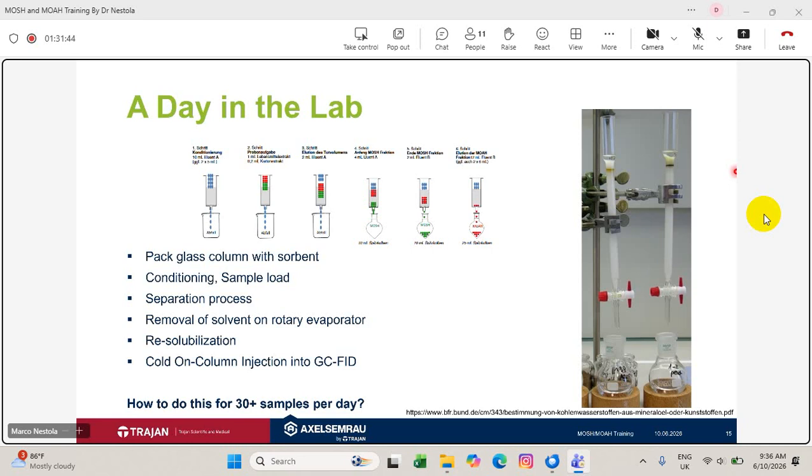You are getting nice alkanes in the beginning, and then they are getting smaller and smaller, because temperature or transfer of the sample from the liner onto the column doesn't work anymore. That's basically what you are seeing there.